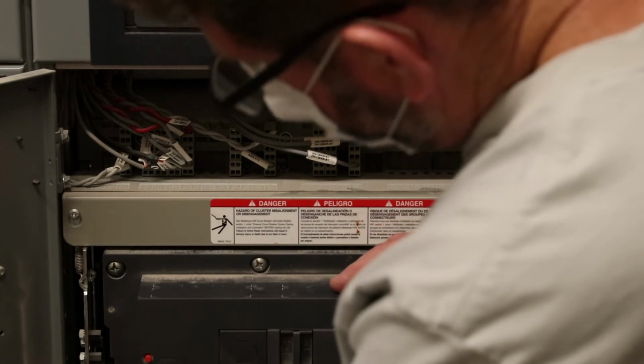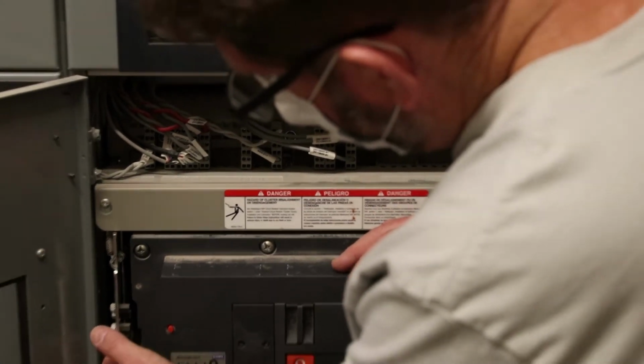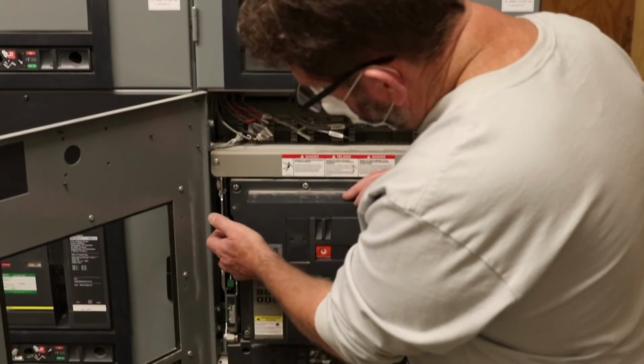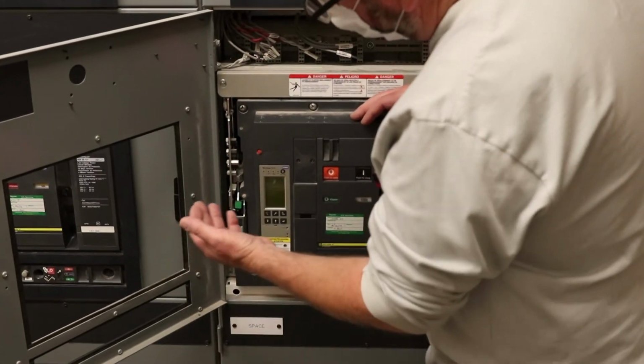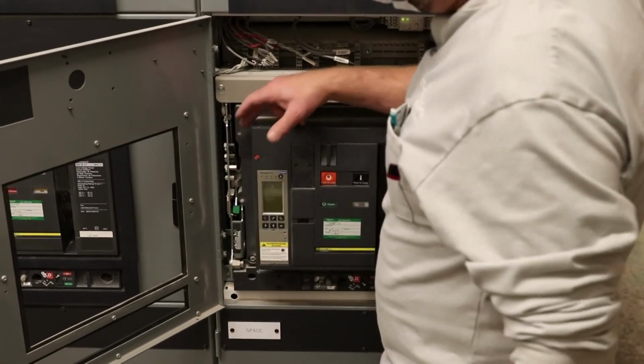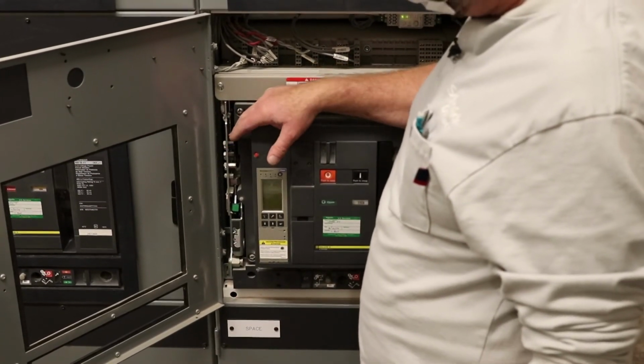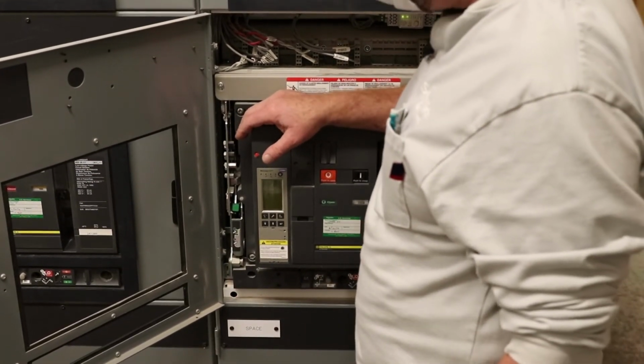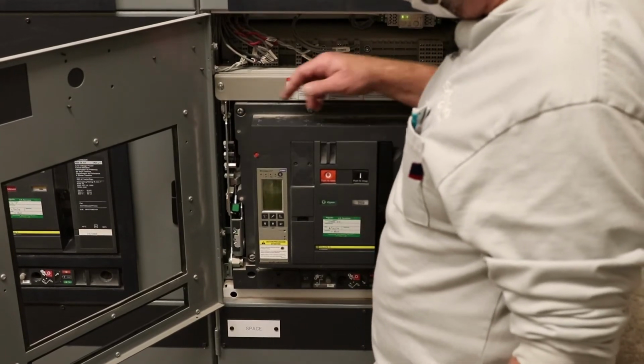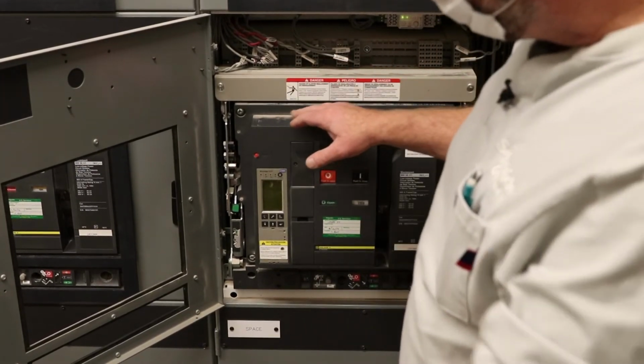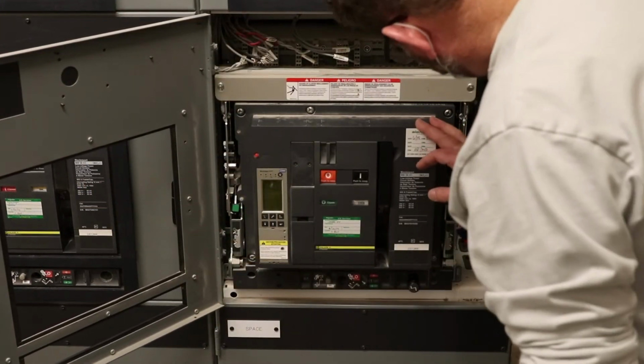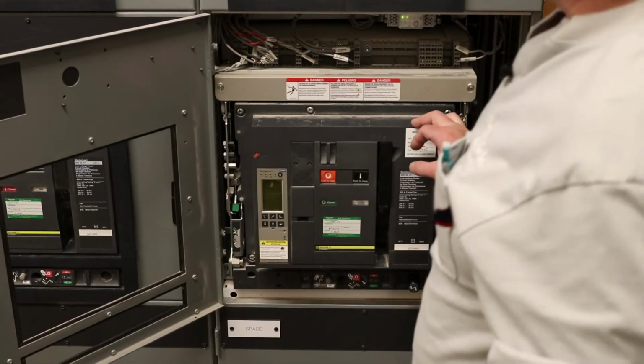Over here on the left-hand side of the cell, these are called a code plate or rejection pins. These are arranged so that you can't put an incorrectly rated breaker into a cell. So you couldn't accidentally put that main breaker at 3200 amps into this cell. This is an 800 amp cell.